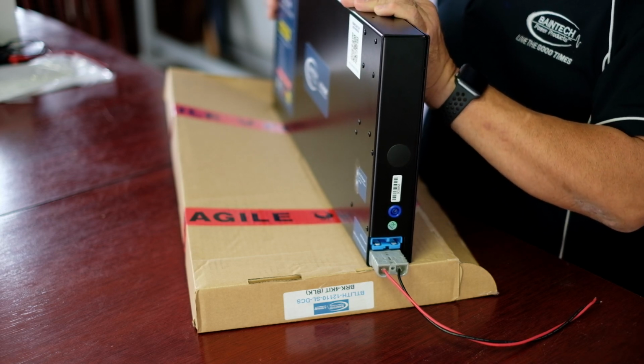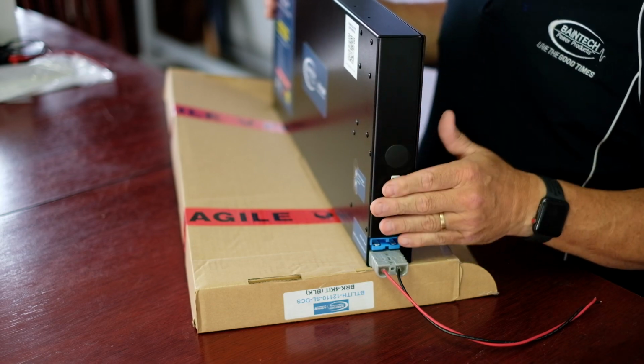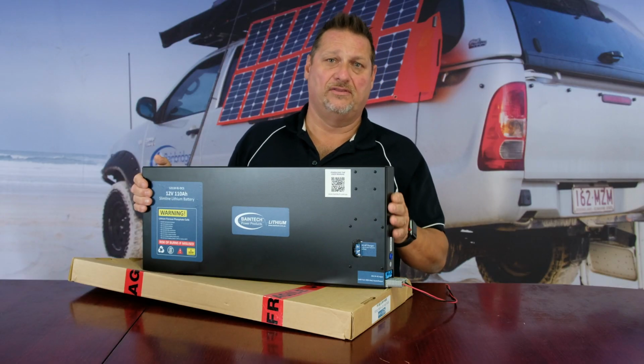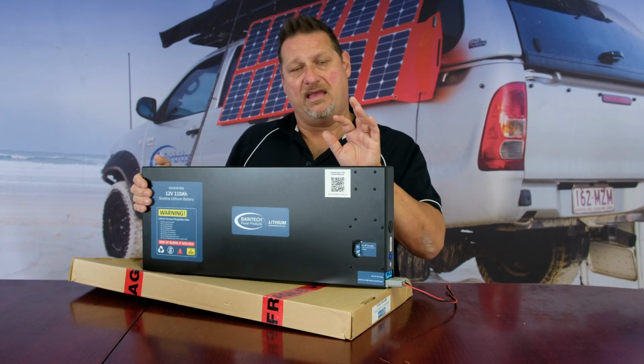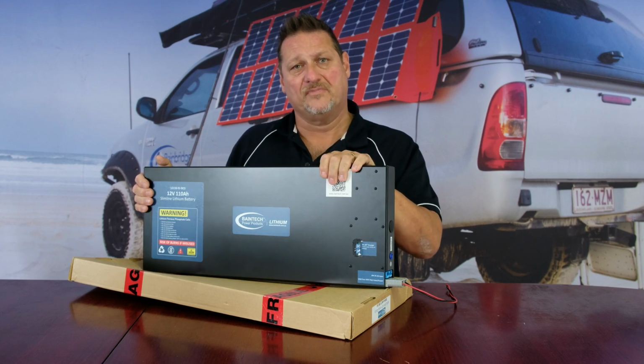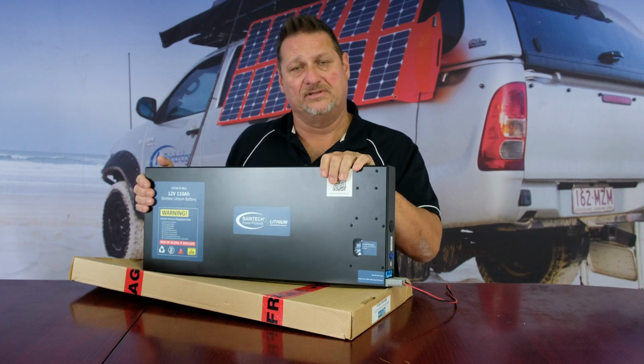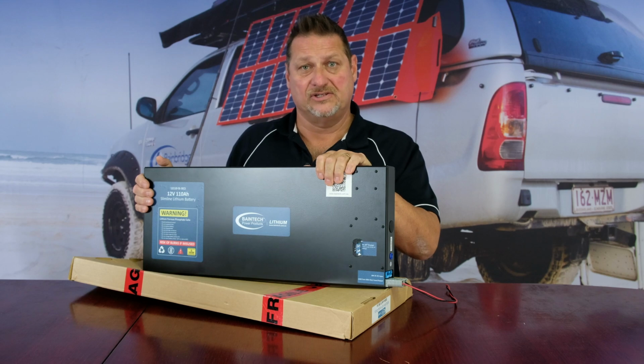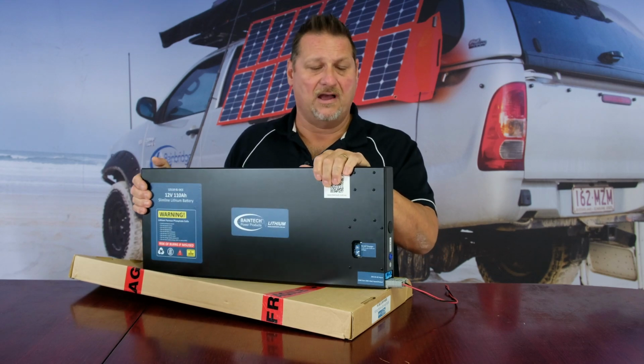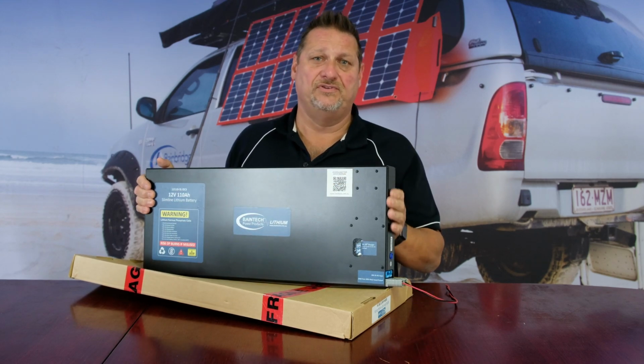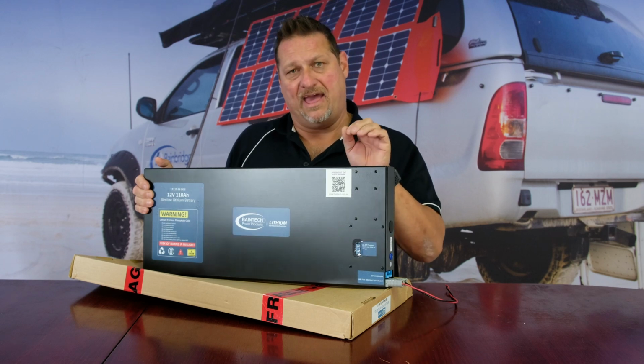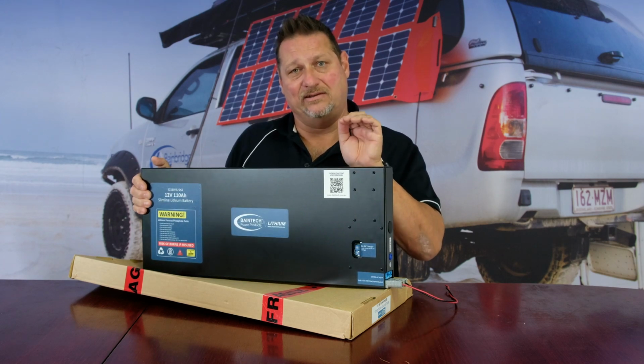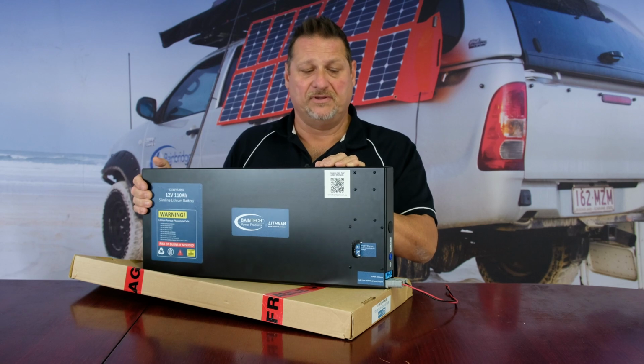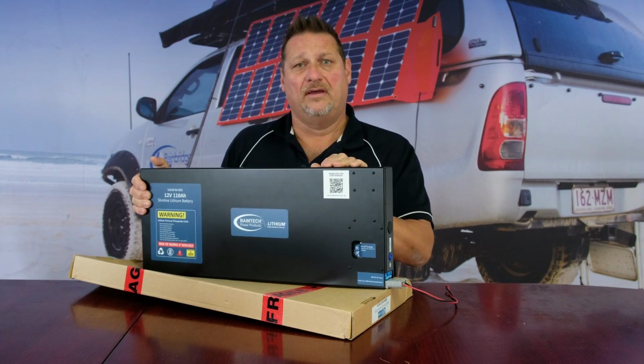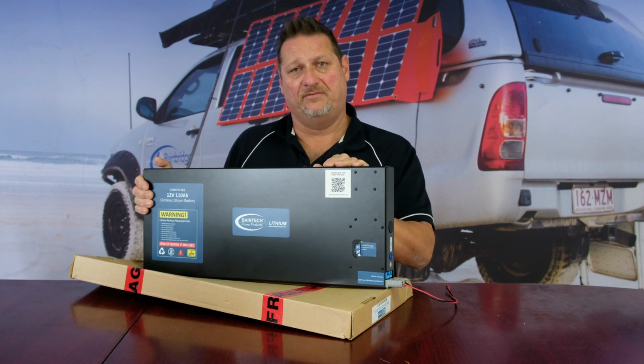Circuit protection. On our very first models of these, we used to have a fuse externally on them. We went away from that and put in a new upgraded BMS that we built specifically for Australian conditions. By doing so, we took the fuse off the end and put a resettable fuse in on the circuit breaker. It's 100 amp because it's a 100 amp BMS, so it literally covers you for the full loads.